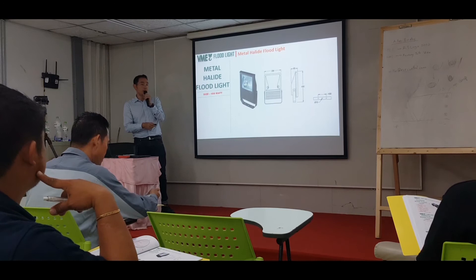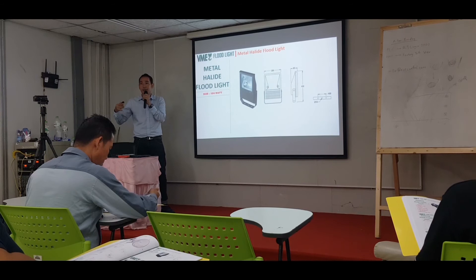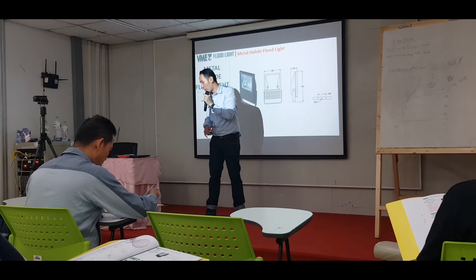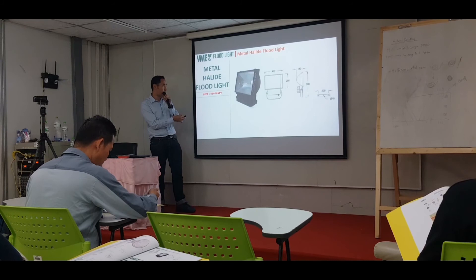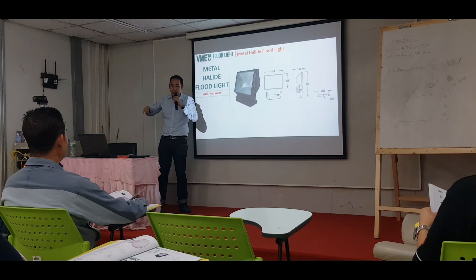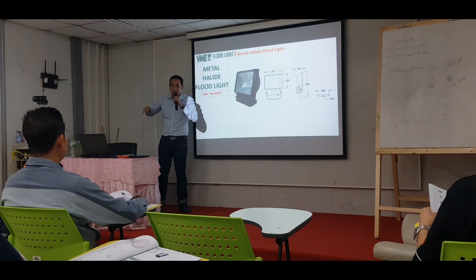What you use is 400 watts. For the small deck area, we are giving 150 watts — just for compound illumination, to light up the service platform or walkway. If you were giving 400 watts there, it would be too bright. So we give 150 watts for that. But for the whole crane compound area and its surroundings, we are giving 400 watts, which would be good enough.